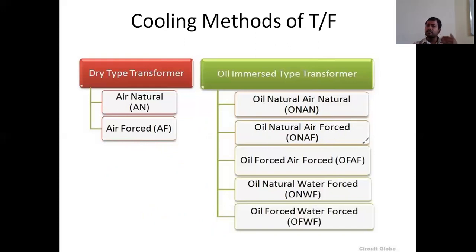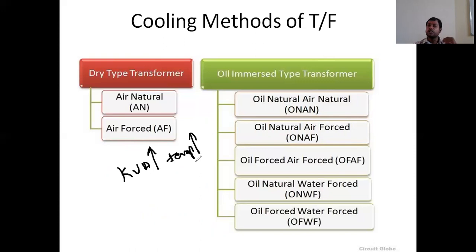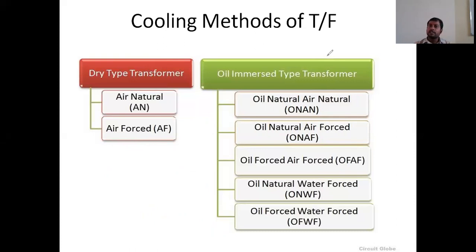As the KVA capacity of the transformer increases, temperature production increases, so we need to use different methods to reduce the temperature of the oil. That is why these classifications exist. The next method is Oil Forced, Air Forced — OFAF — where we need to forcibly send oil from tank to radiators using a pump.